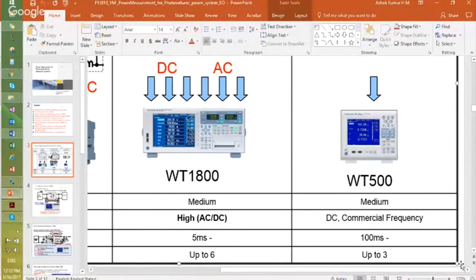I'll give you an example. We have a distribution transformer and a power transformer. Distribution transformer: low voltage, low current. Power transformer: high voltage, high current. So instead of using a WT3000, I'll go with a WT500 for the distribution transformer and power transformer. 0.1% of 440 volts is around 0.44 or 0.4 volts. And for a power transformer at 11 kV or 16 kV, 0.1% of 11 kV.